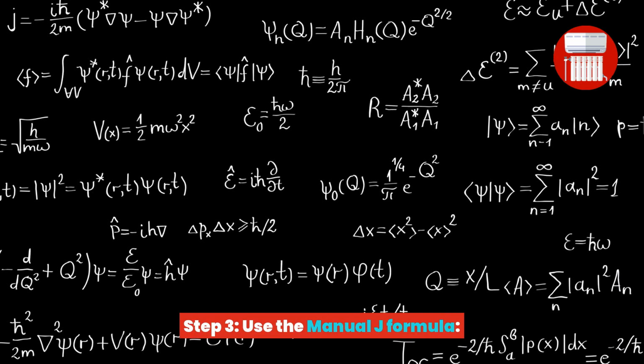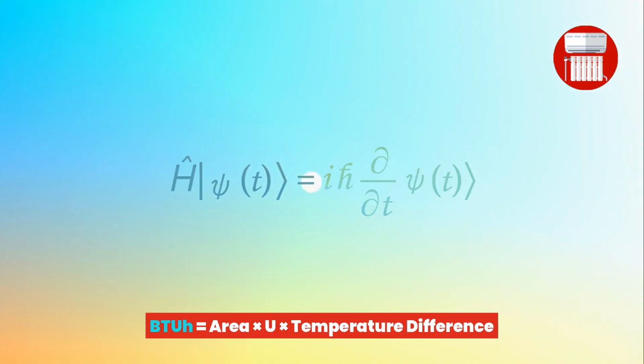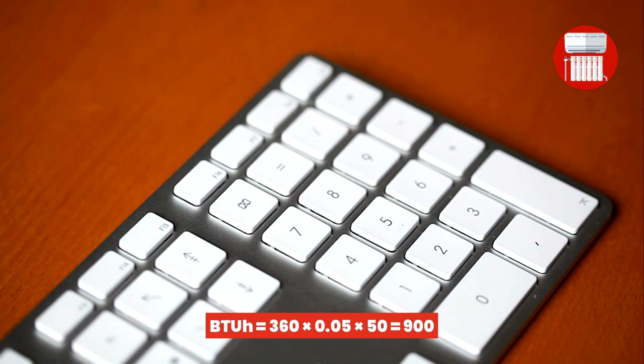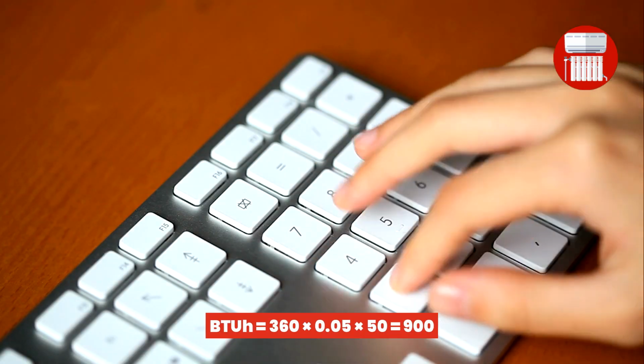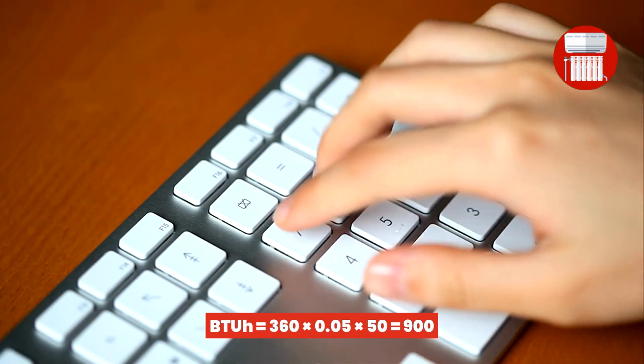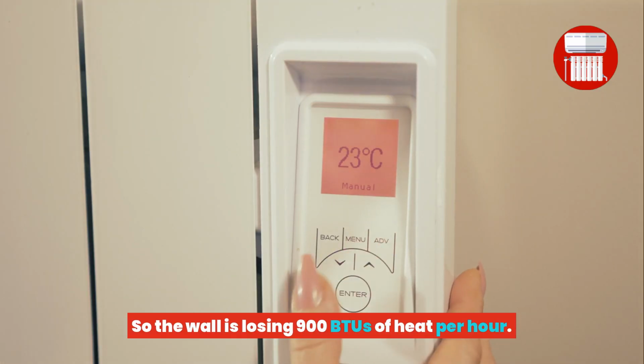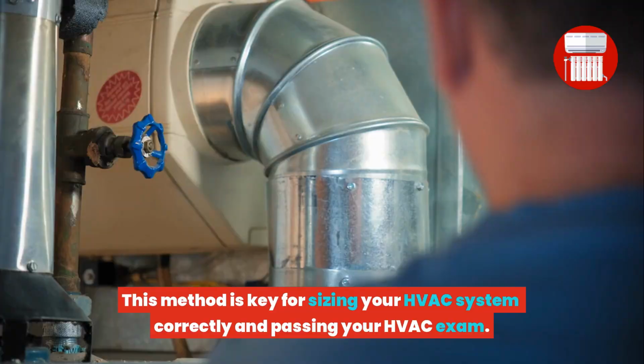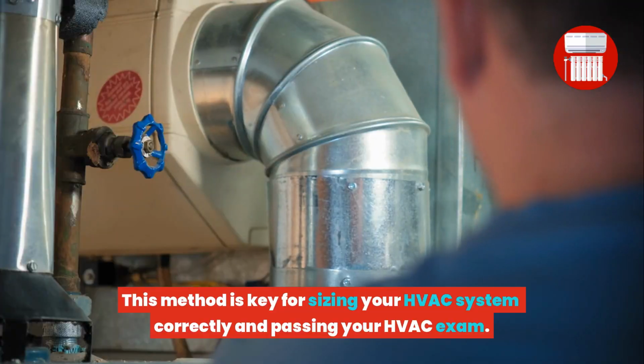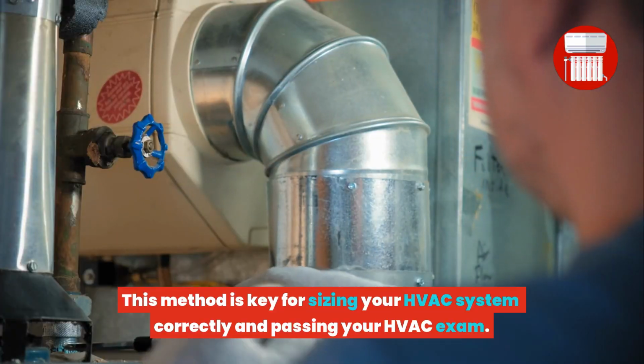Step 3. Use the Manual J formula, BTUh equals area times U times temperature difference. That's BTUh equals 360 times 0.05 times 50 equals 900, so the wall is losing 900 BTUs of heat per hour. This method is key for sizing your HVAC system correctly and passing your HVAC exam.